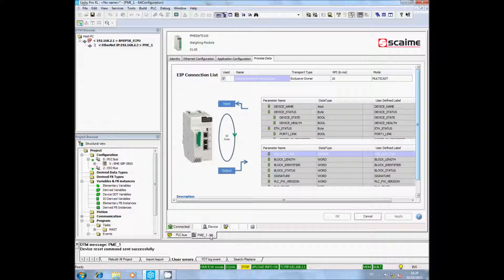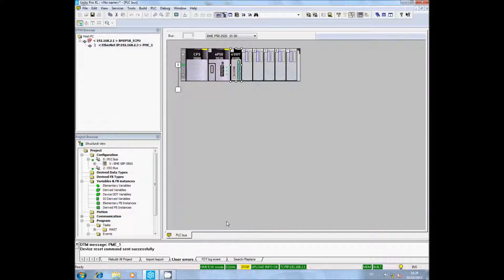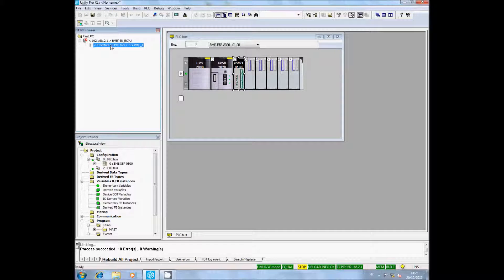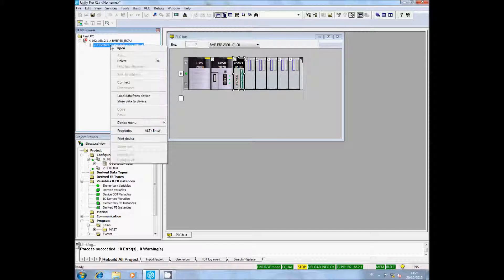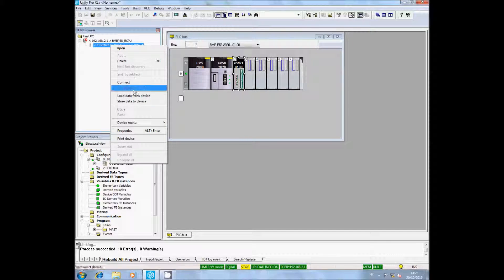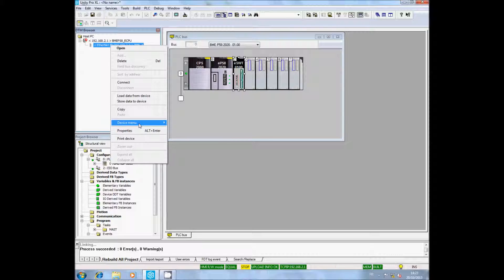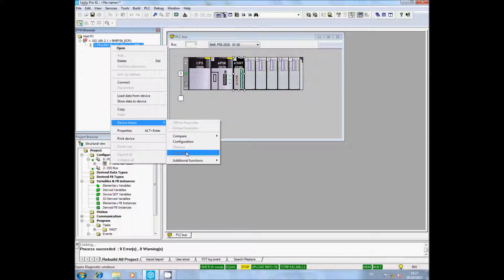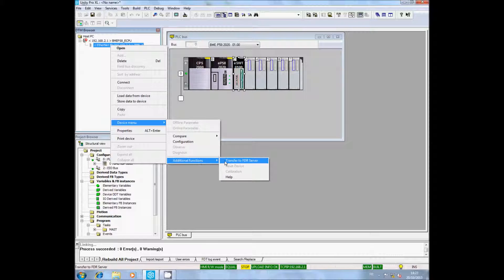After changing parameters, you need to transfer your configuration to the FDR server. For that, right click on the PME DTM, select Device menu, then select Additional Functions, and click on Transfer to FDR.